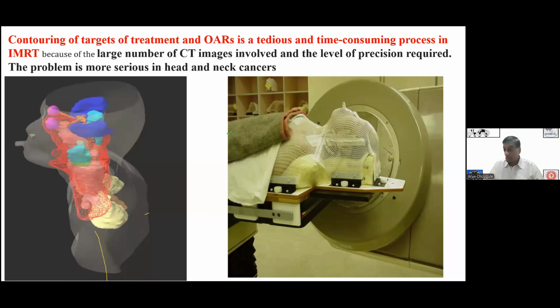Patient positioning and setup daily has to be done. Movement during treatment is an issue, so rigorous and continuous quality assurance procedures are required. Inconsistent QA practice, variability in QA practice across different centers, can lead to inconsistency in treatment quality. Then dosimetric challenges are there: the accuracy of dose calculation algorithms, which algorithms the TPS uses, tissue heterogeneity, and commissioning errors, which, if they happen, will carry on through the treatment.